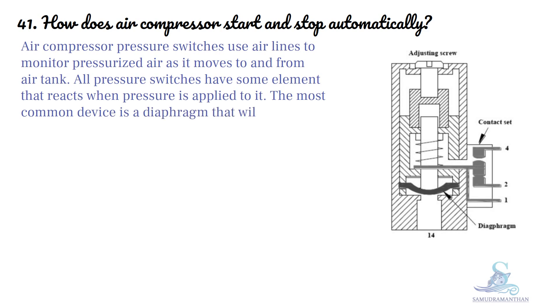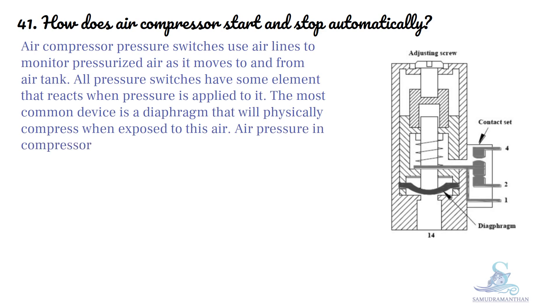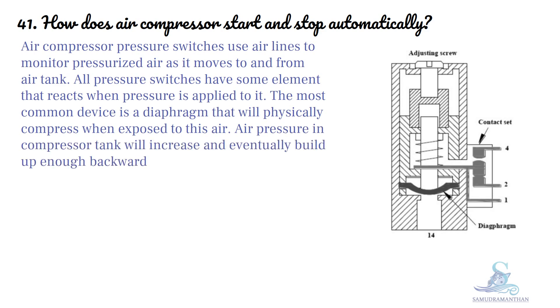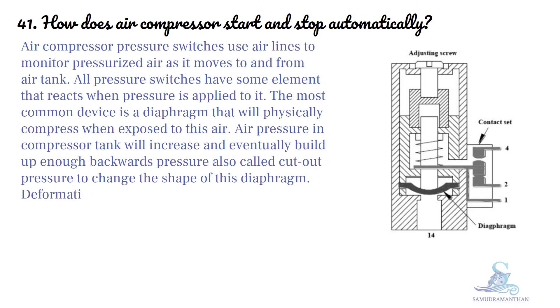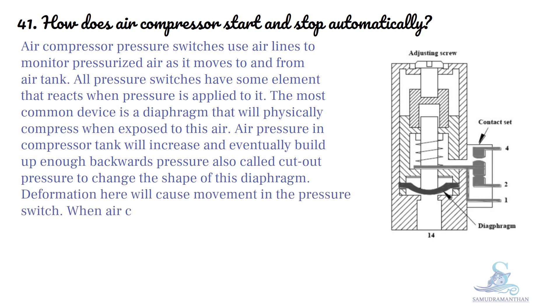The most common device is a diaphragm that will physically compress when exposed to this air. Air pressure in the compressor tank will increase and eventually build up enough back pressure, also called cut-out pressure, to change the shape of this diaphragm. Deformation here will cause movement in the pressure switch.